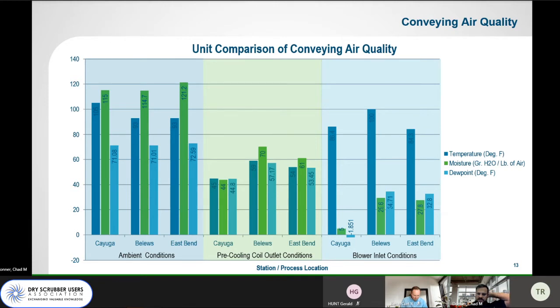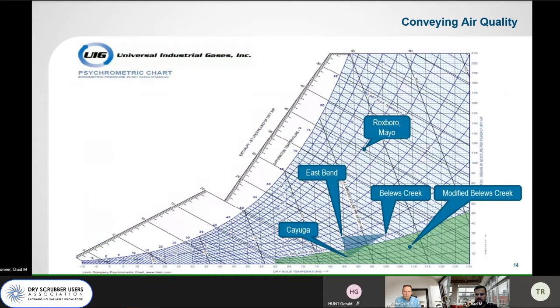I compared the different systems on grains of moisture and relative humidity, and it showed that the system where we changed the set point from 5 to 30 grains of moisture was above that 8% relative humidity point, and the relative level of pluggage and scaling that we saw made sense based on the scaling that we were seeing. So I plotted these results on a psychrometric chart. Cayuga was the 5 grain point, and I've shaded the area below 8% relative humidity in green. Belews Creek was the site with 30 grains, and you can see it's just slightly above the 8% curve. The pluggage wasn't bad, but it was just enough to be annoying.